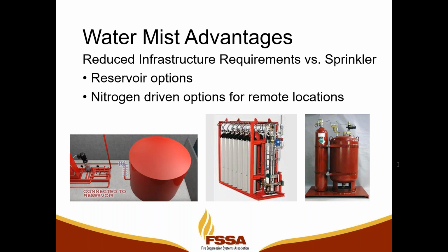So I can just off the top of my head think of a law enforcement facility like a sheriff's department in a remote location on the East Coast where they did not have adequate water supply for a sprinkler system. So they go with one of these package units, and because the motor, the driver of the water, is nitrogen, all they have to have is 24 volts DC to open a solenoid and allow nitrogen to flow through the system and either turn an air motor or push water through the system.